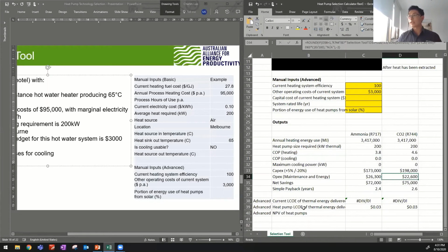We've also got the levelized cost of thermal energy delivered. So here for the heat pump, it's about 3 cents per kilowatt hour of thermal energy. Now we can calculate the levelized cost of thermal energy for the existing system, but we need the lifetime. So let's say the system was initially rated at 15 years when it was brand new, and it costs $8,000 or $80,000 to put in at the start. And we can straight away compare the different levelized cost of energies for the two different systems.